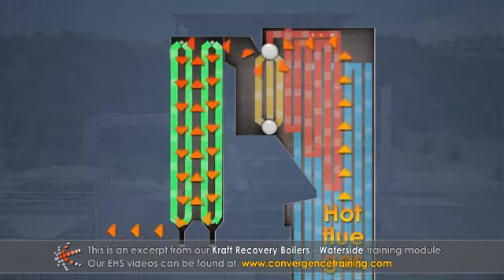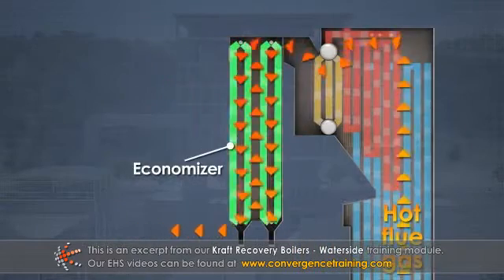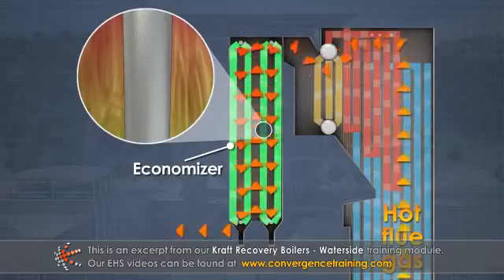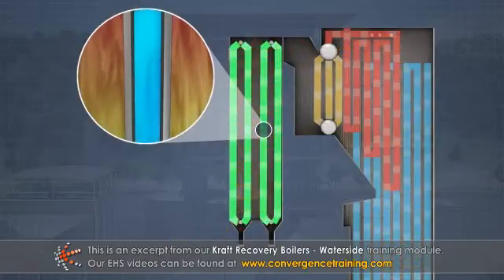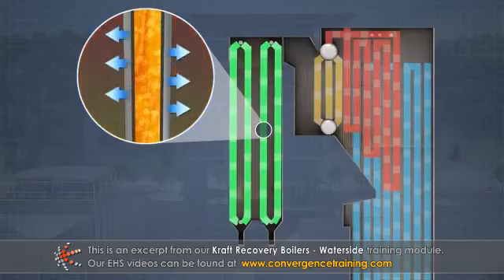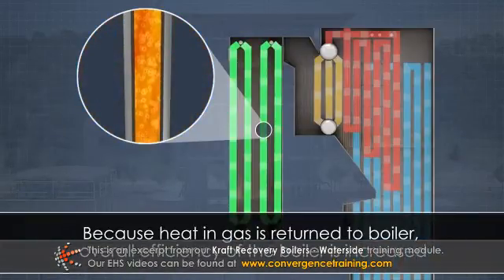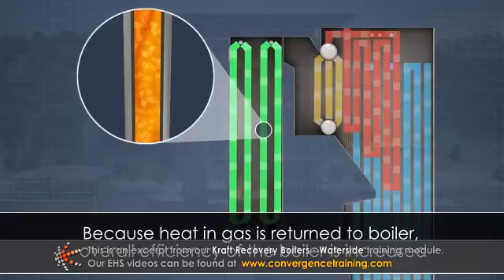This gas flows through an economizer which contains heat transfer tubes similar to the boiler tubes. As incoming water flows through these tubes, the water is heated and the gas surrounding the tubes is cooled. Because some of the heat in the gas is returned to the boiler, the overall efficiency of the boiler is increased.